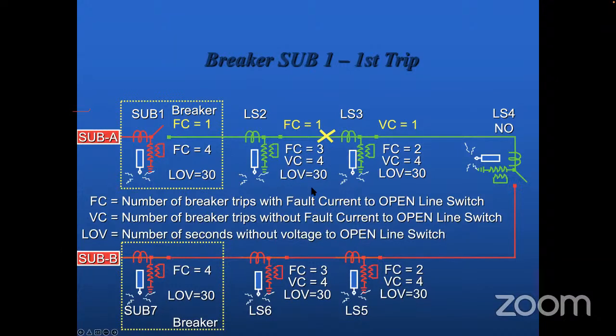So, green indication means the fault is cleared and the feeder is disconnected? No, fault is there, but green is indicating there is no power, no voltage. Okay, so red means there is power. Otherwise normally we'd say red means alarming state and green means normal state.